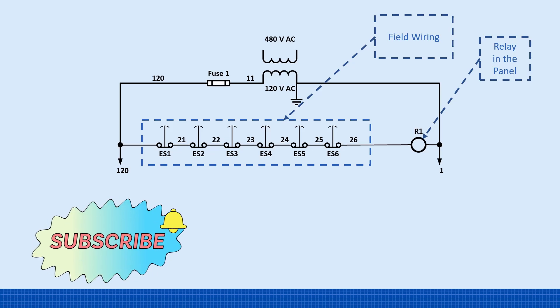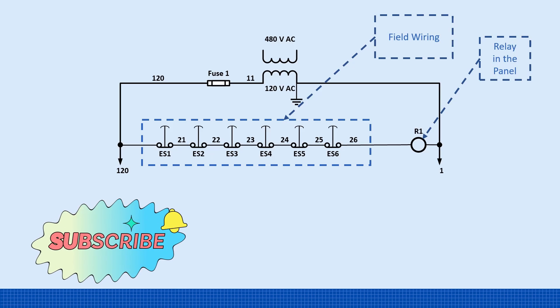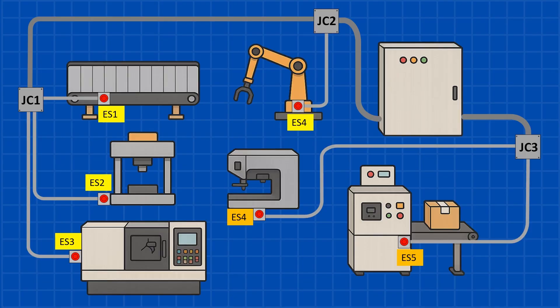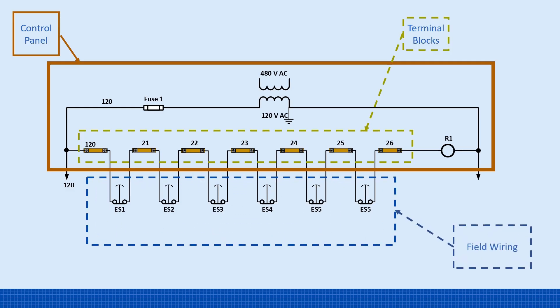And that can lead to hours of downtime. The correct way to wire these systems is to bring two wires from each switch back to the control panel. Then, if you need to daisy-chain, do it at the terminal blocks inside the panel. That way, if there's a problem with any switch, all the troubleshooting can be done right at the control panel, not out in the field.